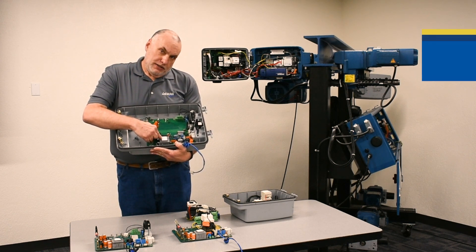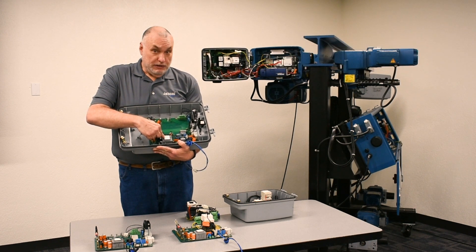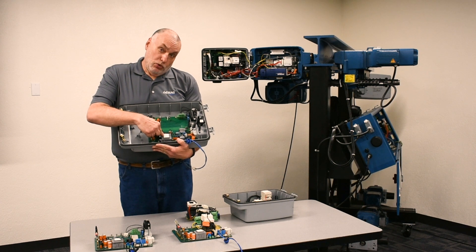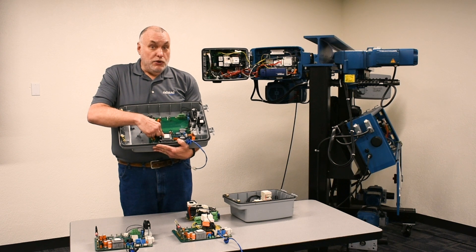In simultaneous independent applications, this firmware level must match between the two hoists. And we can revert a new board back to an earlier firmware level if we know that we have to do it. This only affects firmware levels that are older than 5.11.